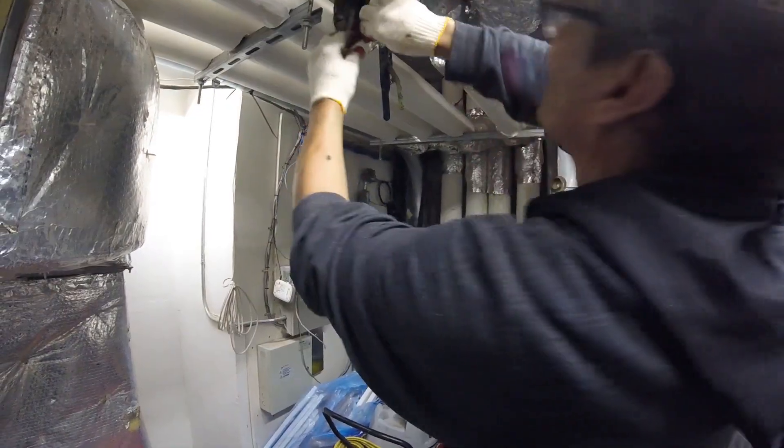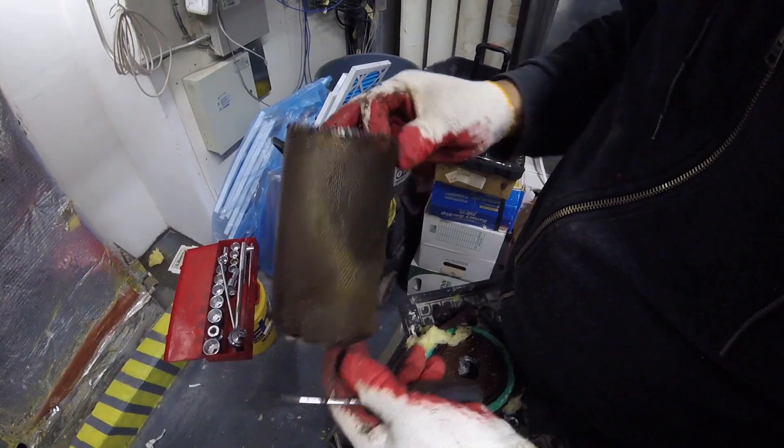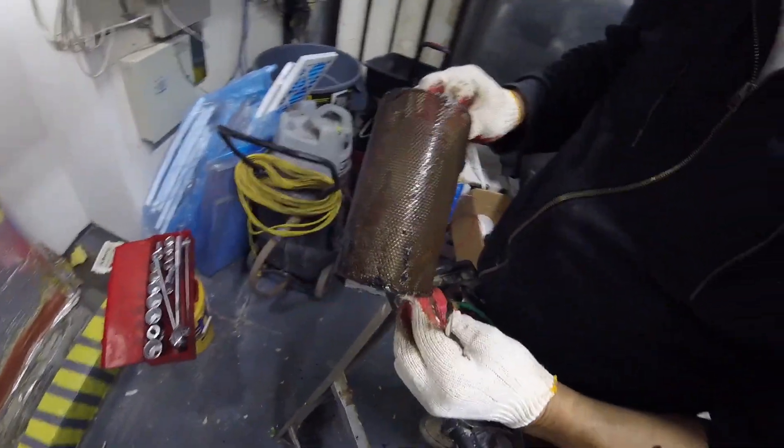You can even see water was coming out from the top — I thought this was dirt. We're going to pull in the strainer while we're at it, not a bad idea. We want to clean this up over here so there's no dirt, and we have a nice seal on our gasket.